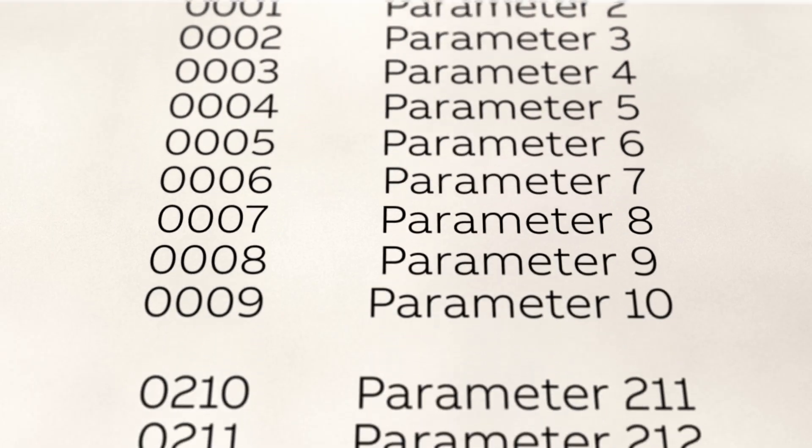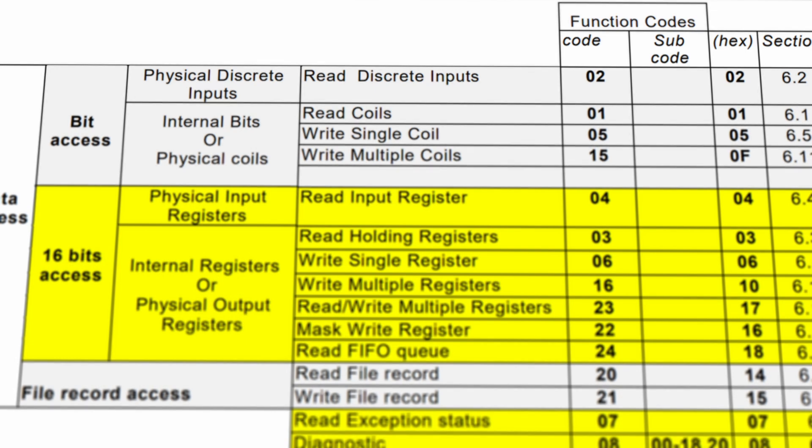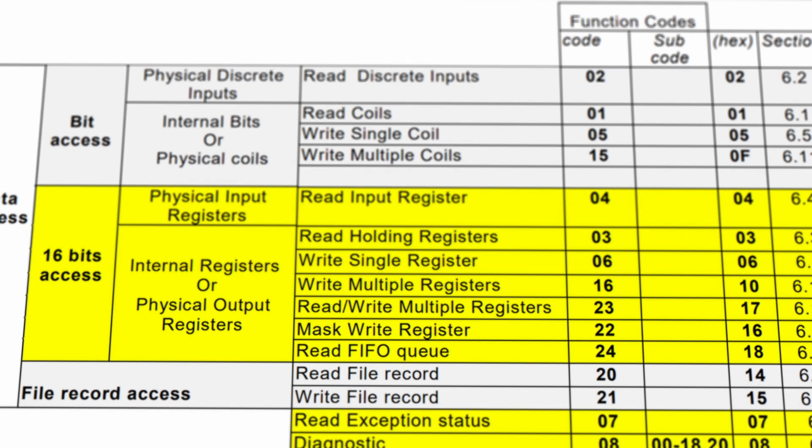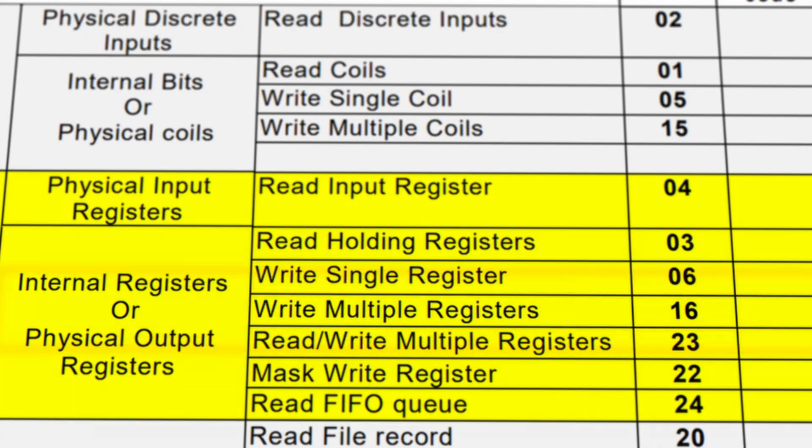A little bit about the Modbus protocol in general. From the Modbus master perspective, a slave device is a long list of 16-bit holding registers which the master can read or write. Depending on what the master wants to do, different Modbus function codes are used. For example, if the master wants to read several registers, it sends a request with Modbus code 3 and the slave replies with the values. If the master wants to write values to several registers, it uses Modbus function 16. There are also bit data types and associated Modbus functions, but nowadays those are either not supported or have limited functionality.